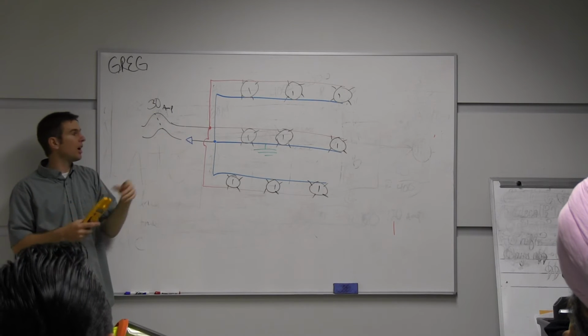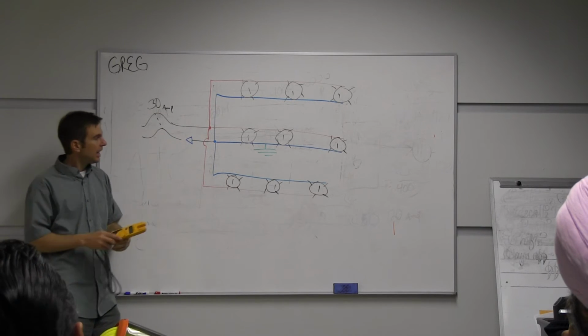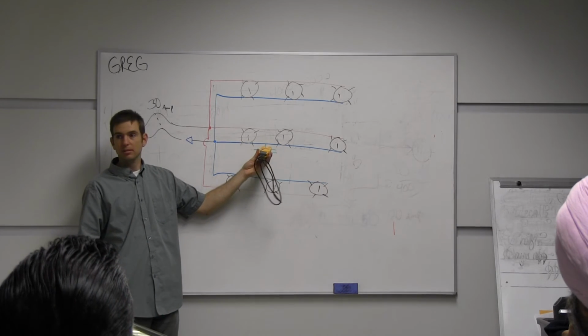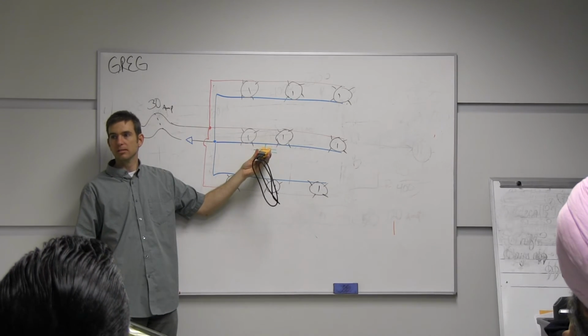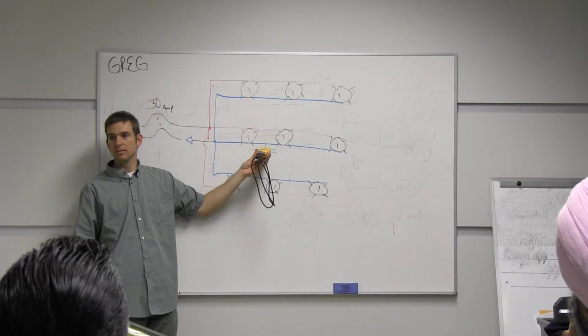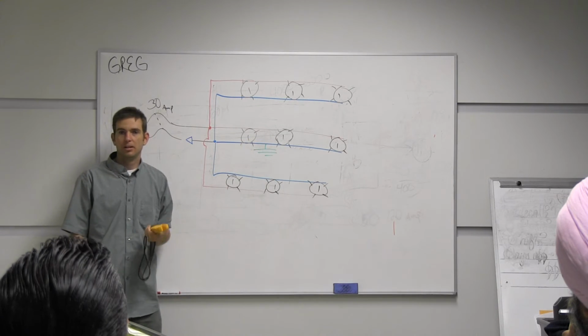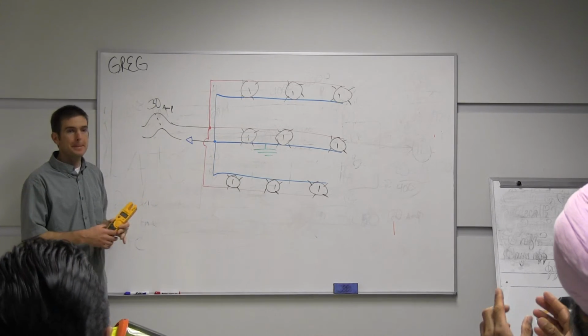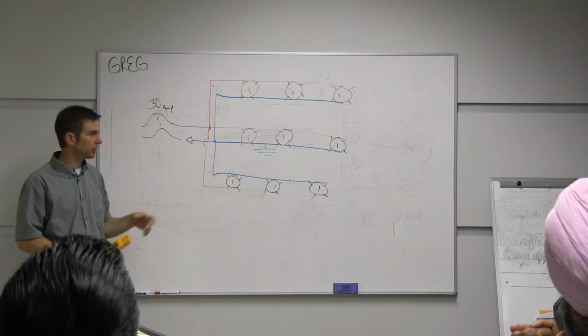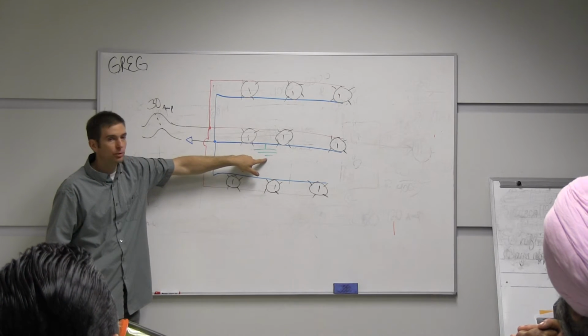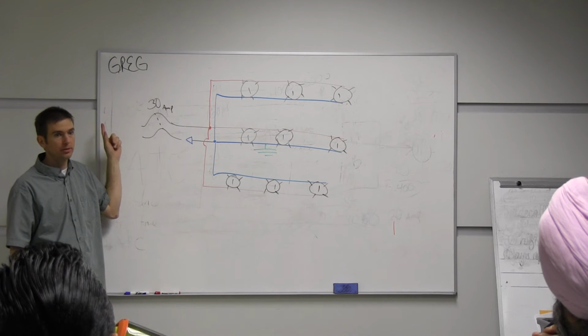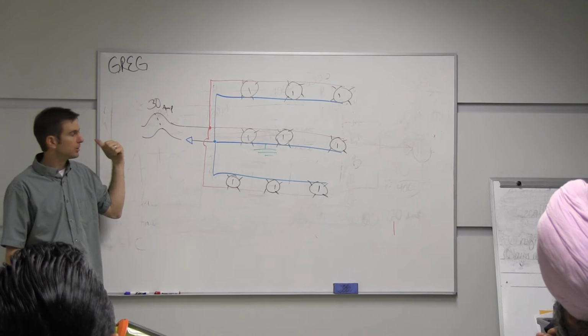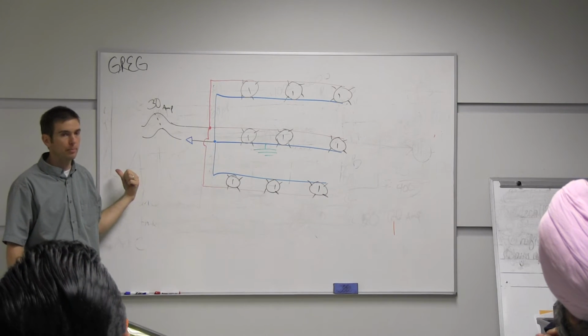Okay, because we took it off the breaker and put a wire nut on it. How many amps do we have here on the ground, going to ground? Is it 9? We have 9. So the circuit will be complete through ground, it means? The circuit is complete because it went through the ground and it traveled back to the source because the source is grounded. So we have ground in the field, we have a path back to the source.